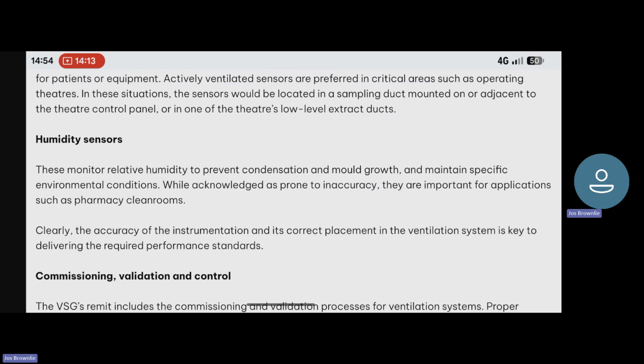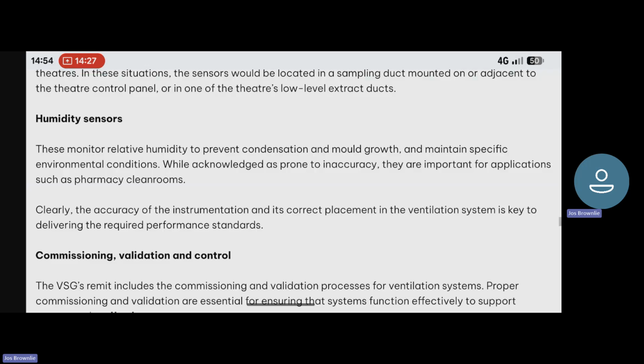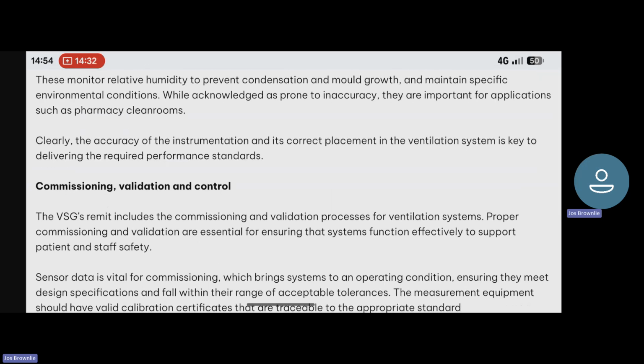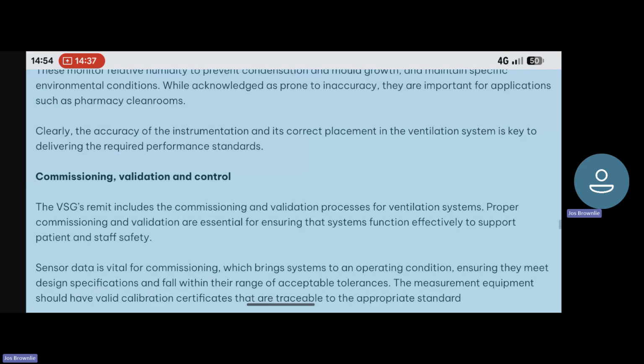Humidity sensors. These monitor relative humidity to prevent condensation and mold growth and maintain specific environmental conditions. While acknowledged as prone to inaccuracy, they are important for applications such as pharmacy cleanrooms. Clearly, the accuracy of the instrumentation and its correct placement in the ventilation system is key to delivering the required performance standards. Commissioning, validation, and control.